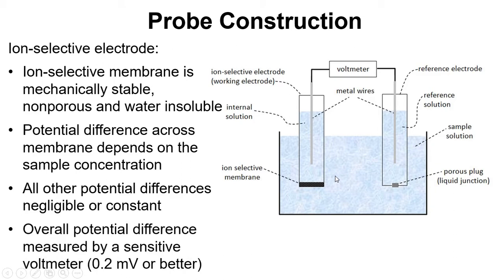The overall potential difference is measured by a sensitive voltmeter at 0.2 millivolts or better. And so overall that is the probe construction for an ion-selective electrode with the reference electrode.